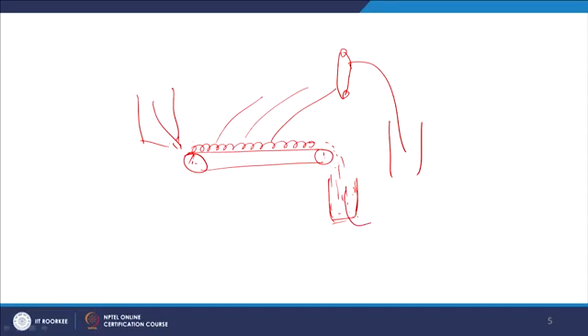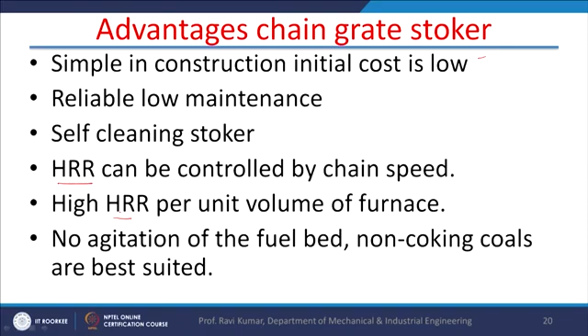So, the advantages of the chain grate stoker are that it is simple in construction, the cost is low, it is reliable, maintenance is low, it is a self cleaning stoker, heat release rate can be controlled by chain speed, and high heat release rate per unit volume of the furnace is possible. There is no agitation of the fuel bed, so non-coking coals are best suited for this purpose.